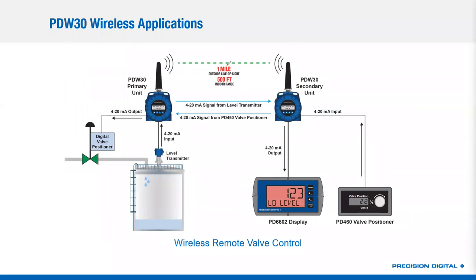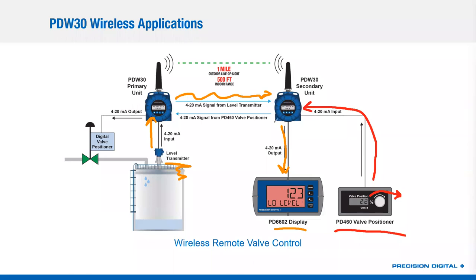In this next example, we're sending 4 to 20 milliamp signals in both directions. I've got my level transmitter with 4 to 20 milliamps going into the primary, traveling wirelessly and being reconstituted back into a 4 to 20 milliamp signal going to a loop-powered display. But in this case, I want the operator at the remote location to be able to change the position of a valve feeding the tank. We've got our PD460 valve positioner, which outputs a 4 to 20 milliamp adjusted by changing the position of a dial. That 4 to 20 output comes into the secondary unit, travels wirelessly back out to the field where it's put back into a 4 to 20 milliamp signal going to a digital valve positioner. So I've got two 4 to 20s — one going in each direction through the wireless bridge.